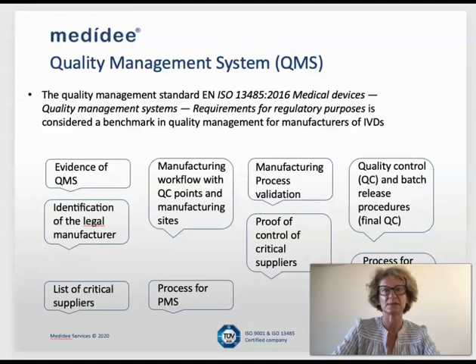In the technical documentation, we will first need a description of the device. We will need to understand what the product is which will be put on the market, and also what configuration and accessories are required in order to make the device work. So we'll first need the identification of the device. It means the name, and also the reference number, and I really underline that we need a reference number. I've recently reviewed some technical documentation, and in fact I've seen that the device had no reference number, so this is not possible.